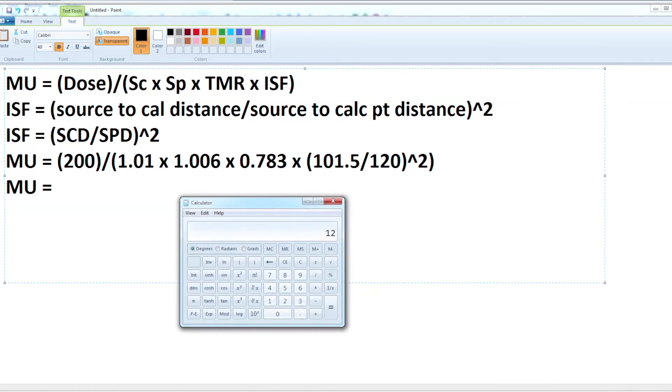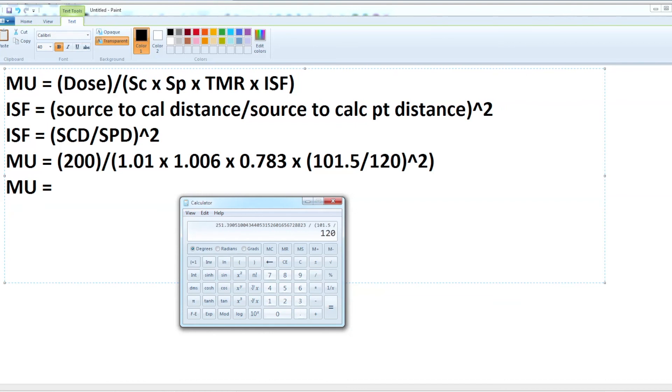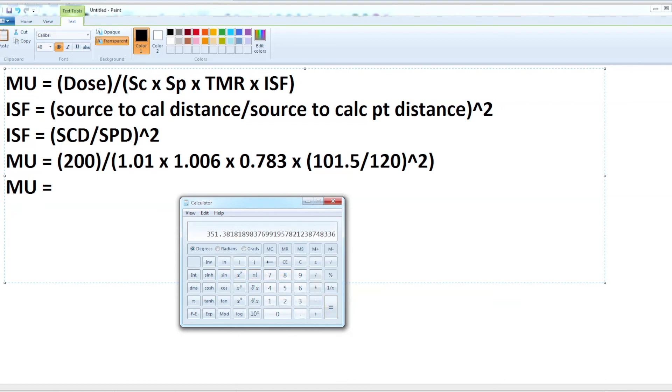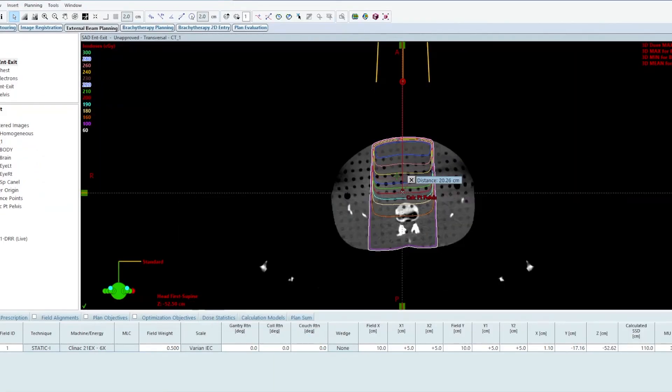If I come in here and say 200 divided by 1.01 divided by 1.006 divided by 0.783 divided by 101.5 divided by 120 in parenthesis squared, I get 351 monitor units.